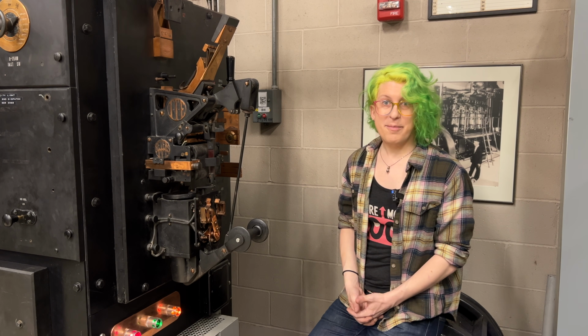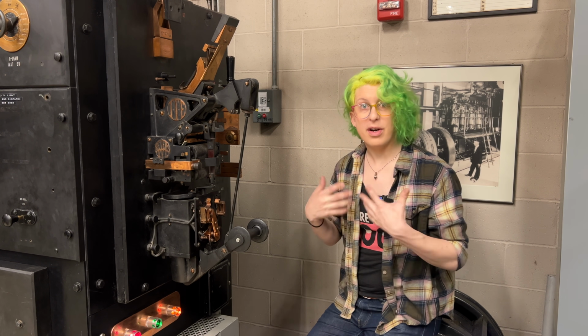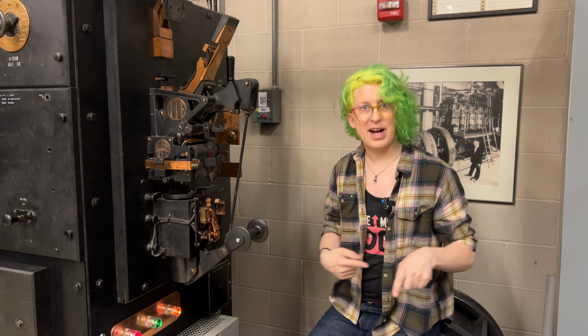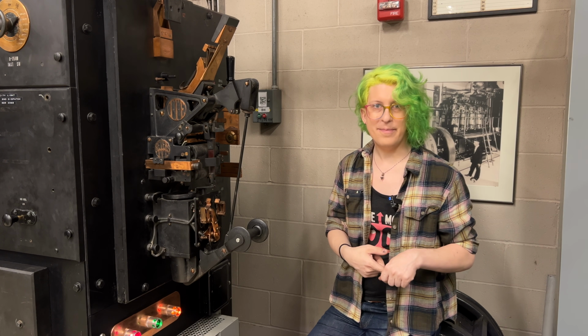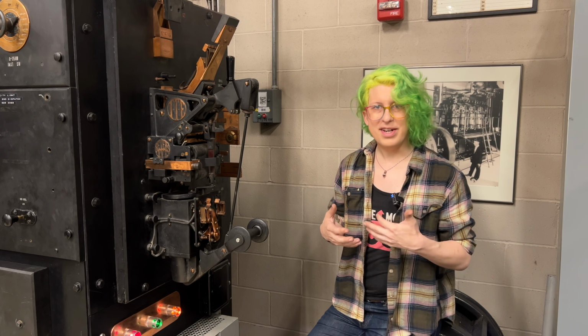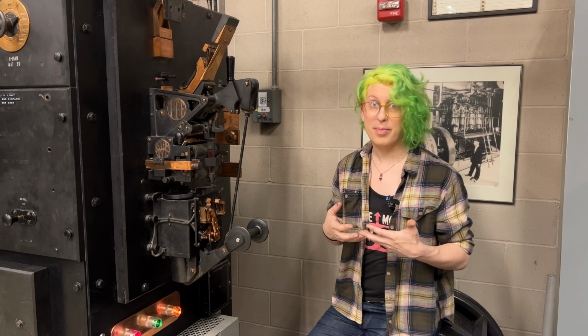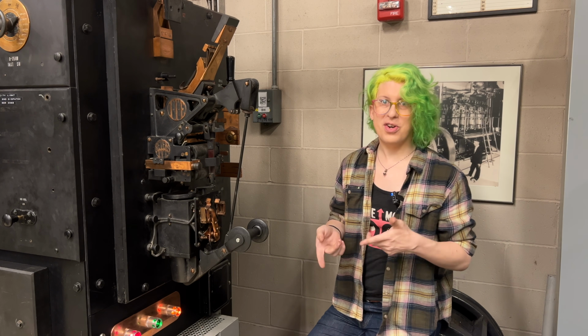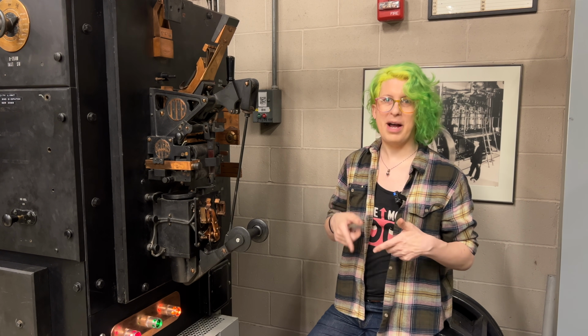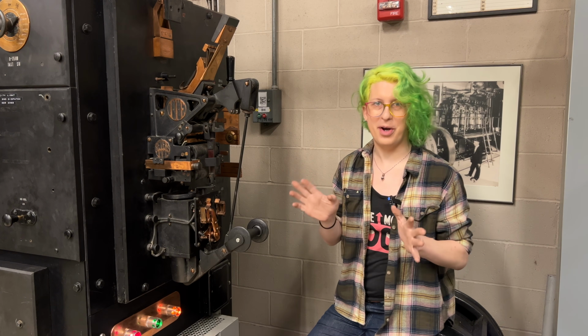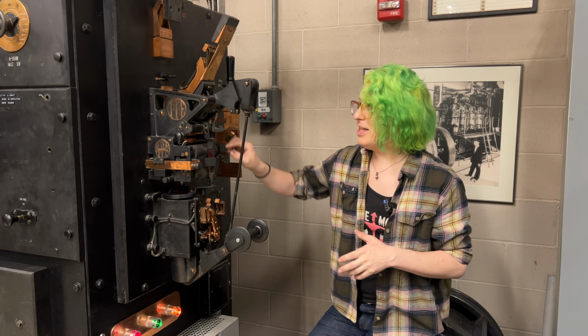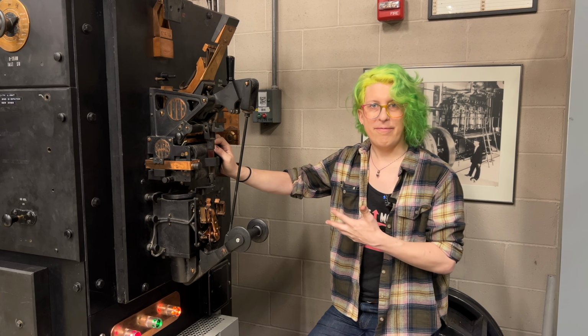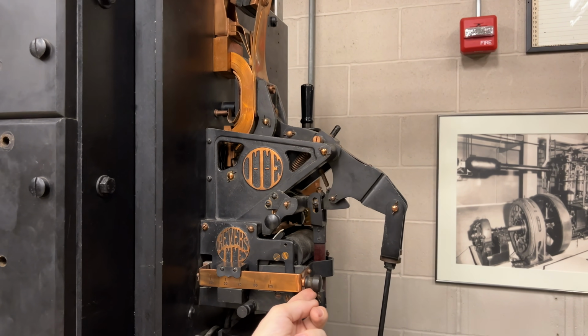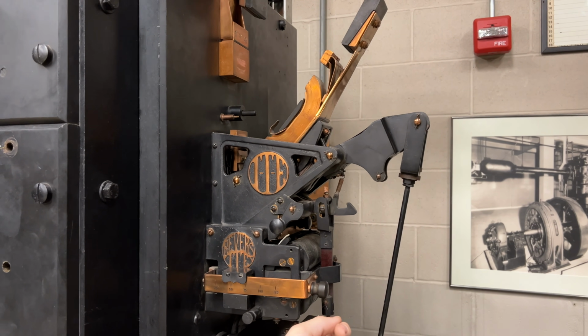The second problem is that the batteries could get overcharged enough to overcome the charging current from the generator and produce back EMF. Back EMF is voltage pushing in the reverse direction from the batteries into the generator. There's always a little bit of this back EMF inherent in the system, but when it becomes excessive, it's a problem. One of the main issues is that we could start turning the generator like a motor and try to send power upstream to the power company, which is a huge no-no. In the circuit breaker, these coils here react to back EMF, and when it reaches a certain tripping point, the armature will open the breaker and open the charging circuit.